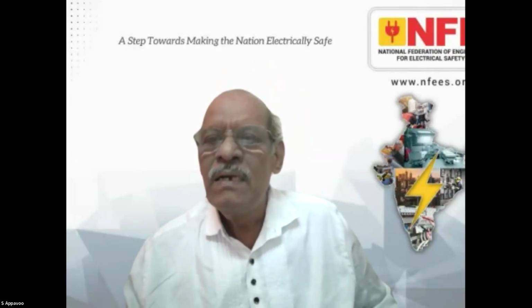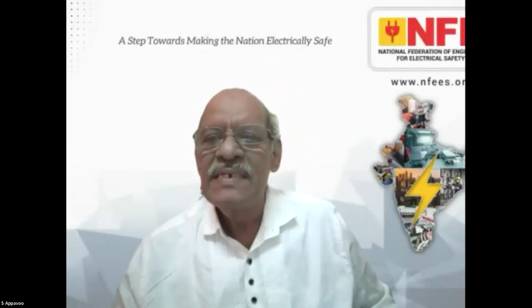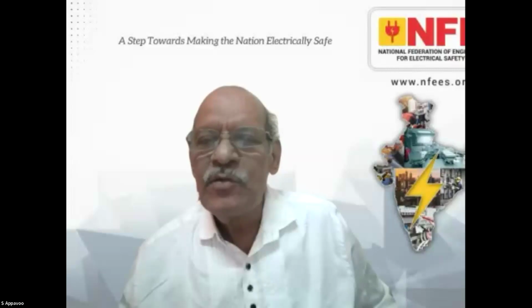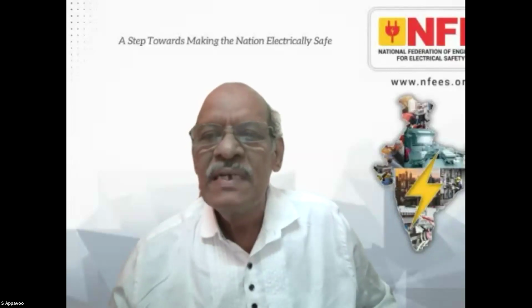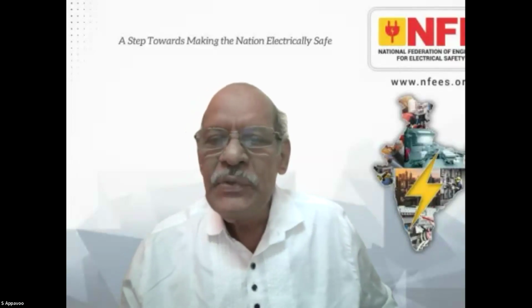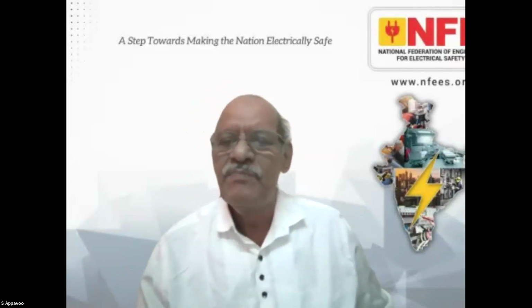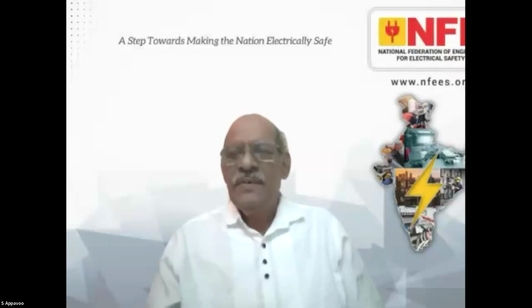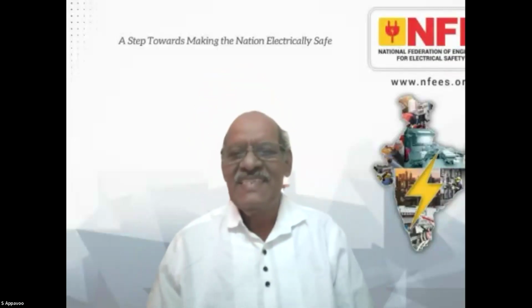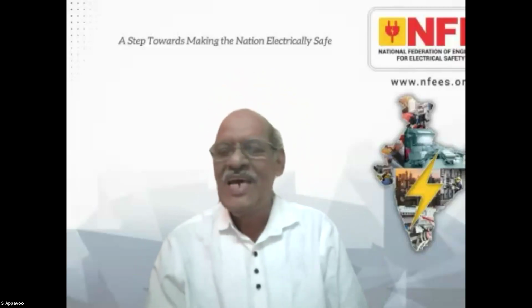Okay, next question. There is one question from Harshad Patel. Can you explain the size of the down conductor of an LPS system? You can have a minimum of 8 mm, 8 mm square CSA is more than enough. It is for mechanical strength. 8 mm is the current minimum, but it is recommended to have 10. You can have 10, that is more than enough. You don't need anything big. It should not erode away due to the normal external atmosphere and other things. Some mechanical rigidity should also be there.